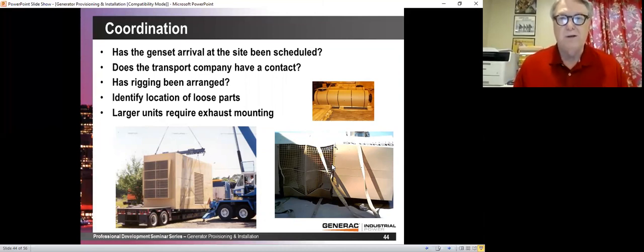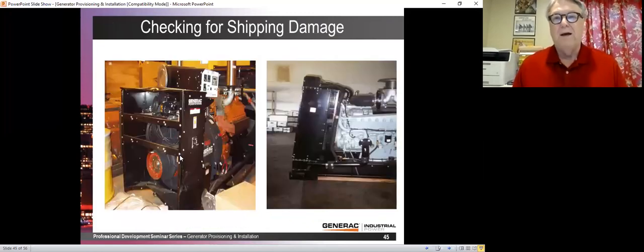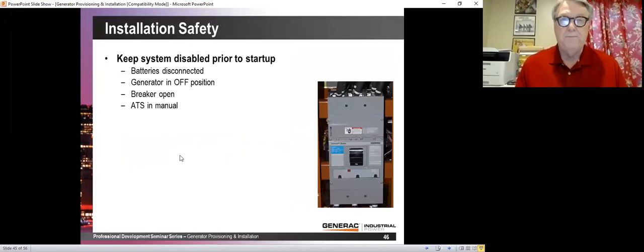Coordination, we want to make sure that the rigging has the spreader bar up here. You can see that here's one that didn't have a spreader bar, and then those lines, the whole weight of the generator is on that sheet metal in the enclosure, and it just collapses. Yes, we've seen that before. This is a generator that was dropped.